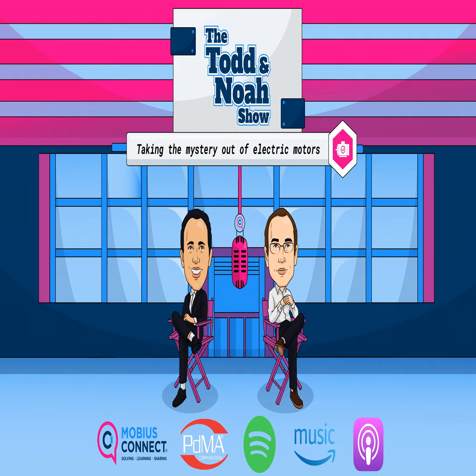The nice thing about this, we always tell you to develop a relationship with your motor repair facility, because you just mentioned a whole different array of rotor types. And what's not on that nameplate is the number of rotor bars. So to understand how many rotor bars there are is instrumental in some of our other data collection points, like rotor bar pass frequency, or even to help with pole pass sidebands if necessary.